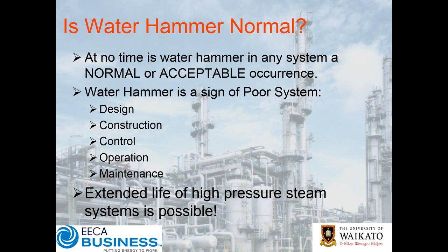To reiterate: you can extend the life of your high-pressure steam assets. To give an example, if you go to New York City, like many other cities in the Northeast, they actually have steam as a utility — one of the largest reticulated steam networks in the world. They have steam valves in that system where they get and expect 20 years of service out of those valves without them being re-kitted on an annual basis. Through good design, good specification, good control, good operation, and good maintenance, these things are achievable.